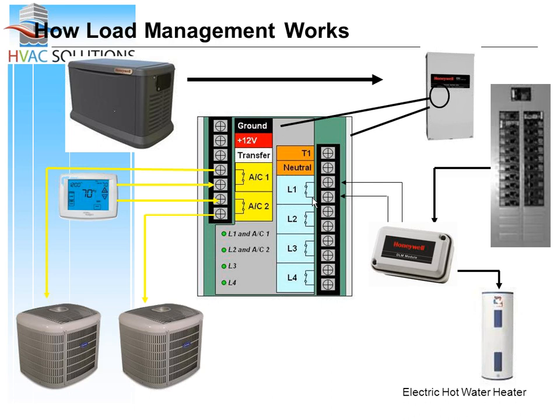So what it's going to do is shed everything that's on this circuit board, and it's going to wait a few minutes, and then it's going to slowly bring them back on. So AC1, L1, L2, L3. Maybe it knows that L3 was the problem, so it's going to skip down to L4. And let's just say we don't have an L4. So everything's running except for L3. Half hour later, it'll come back and double check that L3 and see if enough things have changed on the panel to make it possible to run L3.